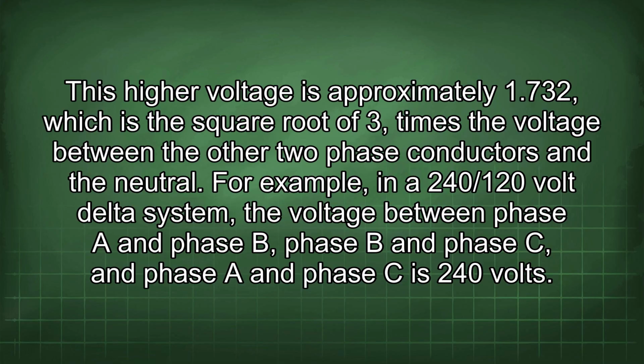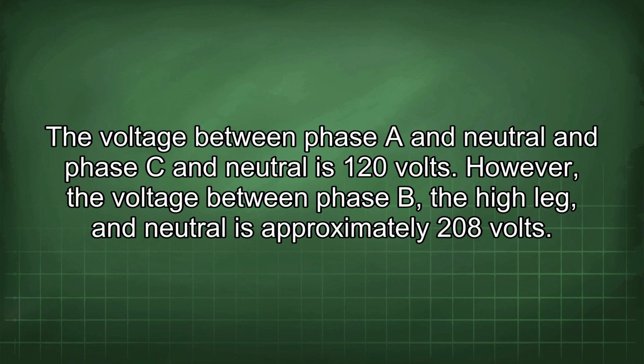For example, in a 240/120 volt delta system, the voltage between phase A and phase B, phase B and phase C, and phase A and phase C is 240 volts. The voltage between phase A and neutral and phase C and neutral is 120 volts. However, the voltage between phase B, the high leg, and neutral is approximately 208 volts.